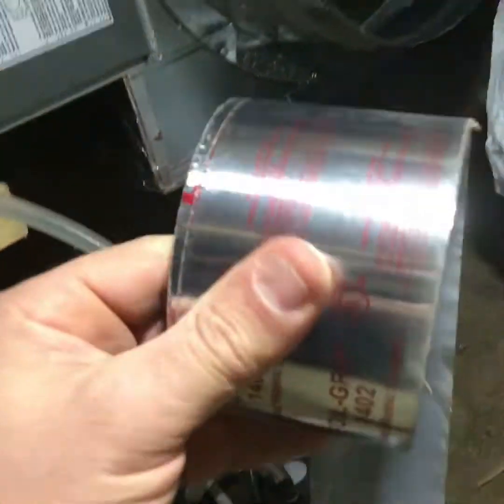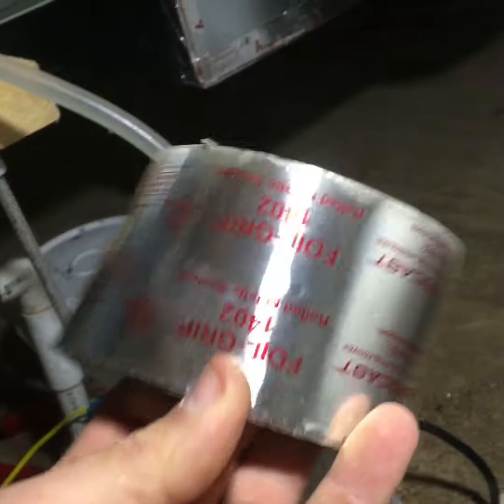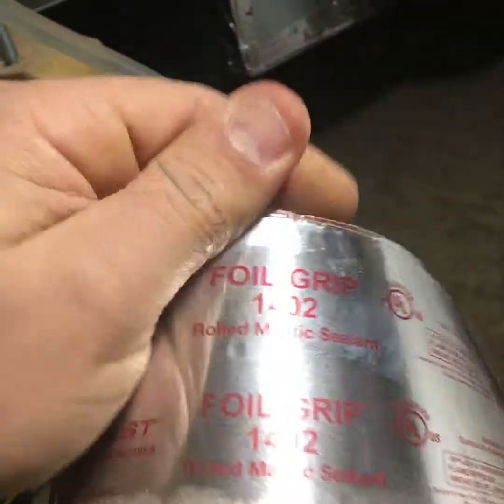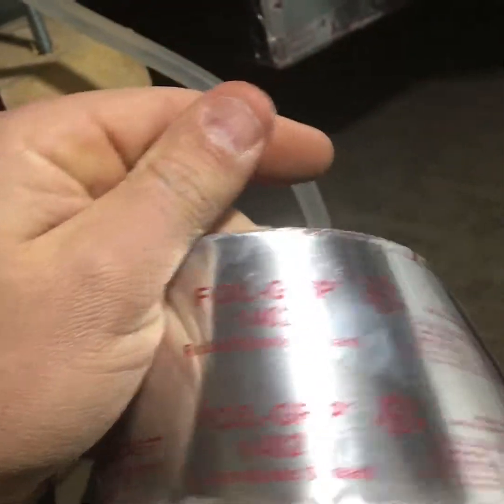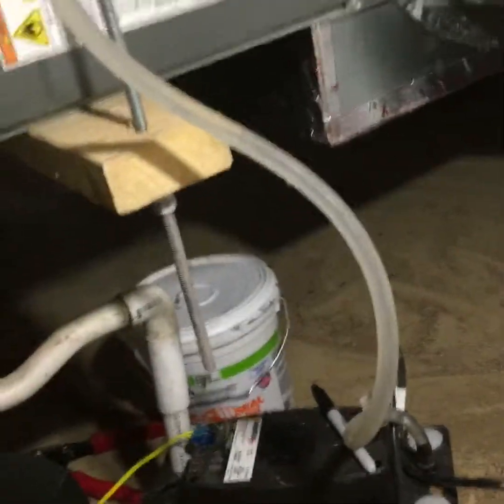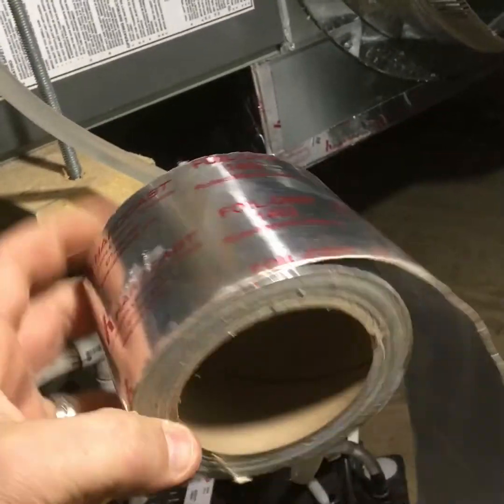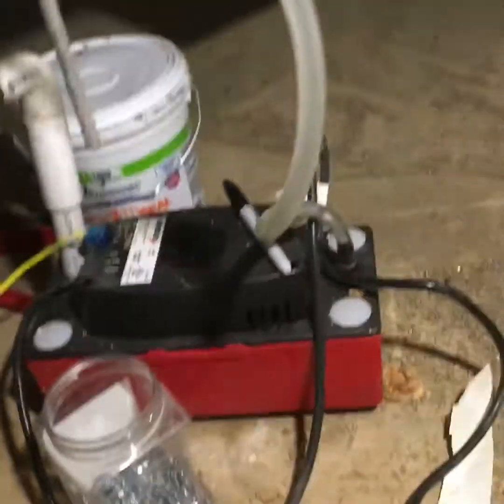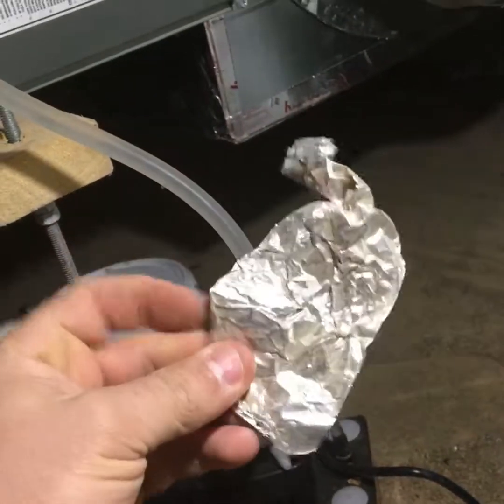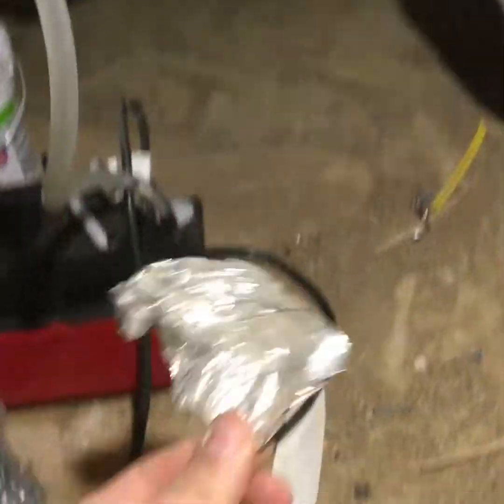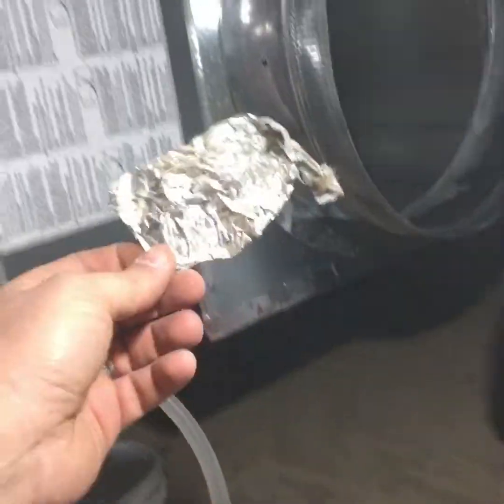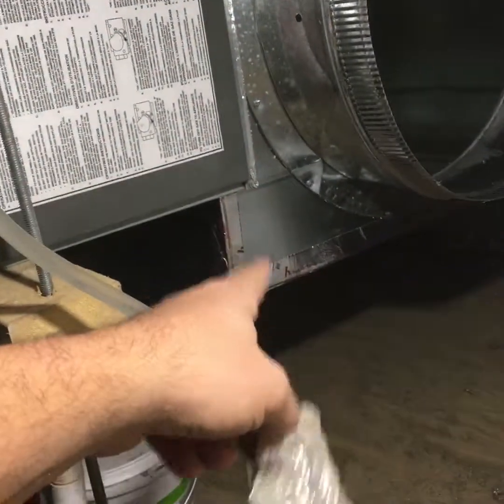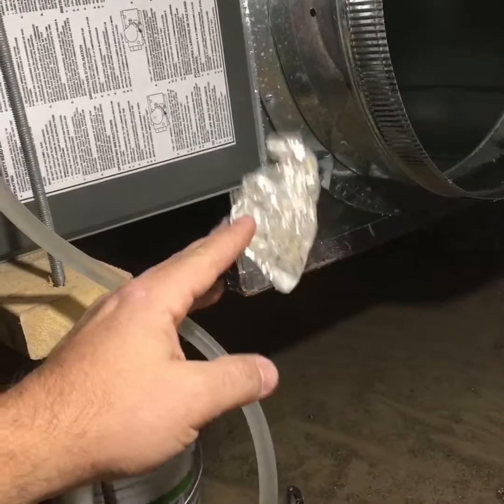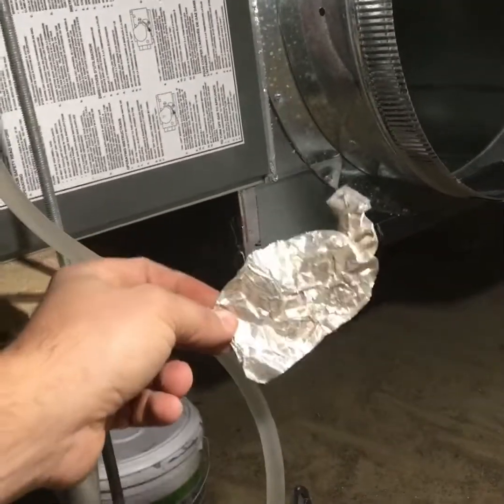And then on my airflow, on my ceiling, I use a lot of, the manufacturer is Hardcast, and it is their 1402 mastic sealant. Mastic tape is what we call it. It is 2 to 3 times more expensive than your old standard foil aluminum tape, but it's worth every penny. This stuff right here will come loose. It'll peel off of metal ductwork, especially if that ductwork gets some condensation, and it'll just peel right off.